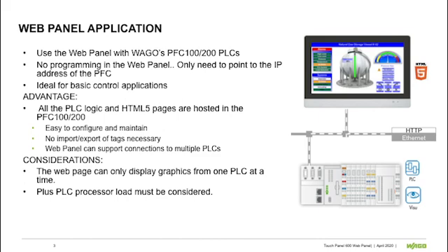The other thing to think about is that the PLC processor load must be considered. The processor needs to manage and execute the PLC logic as well as the web server. So, with more complex applications and systems with a large number of display pages, engineers will have to be mindful of the amount of demands placed on the processor.